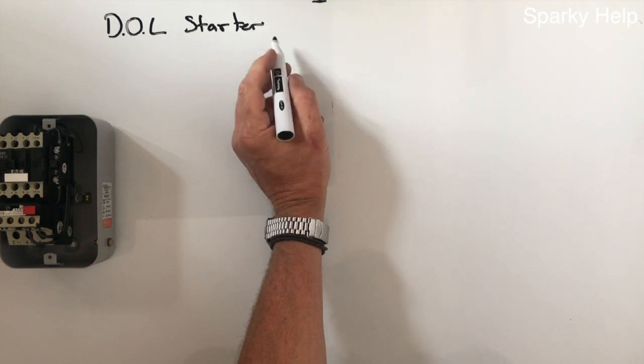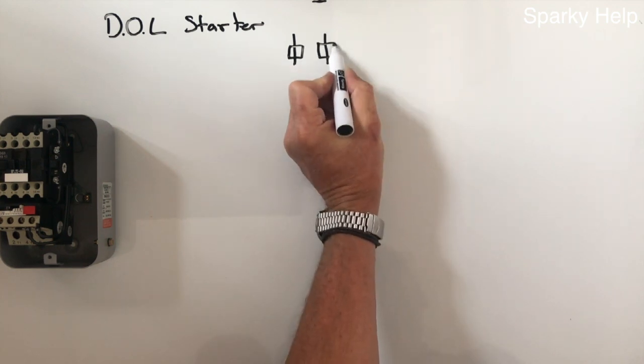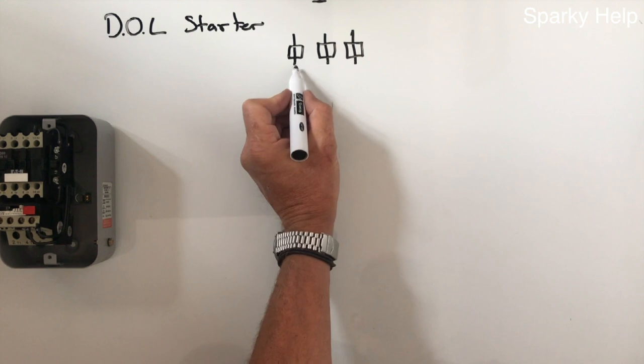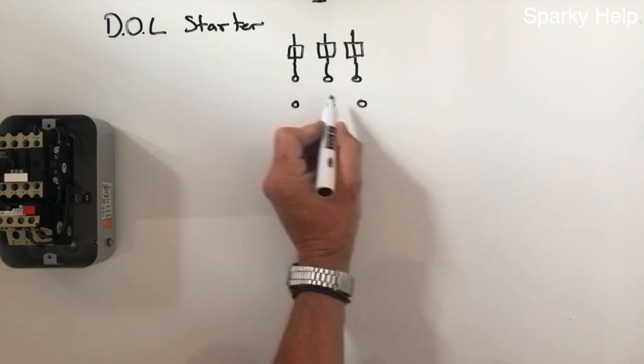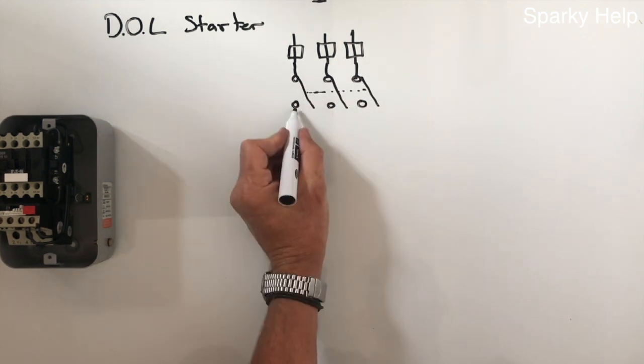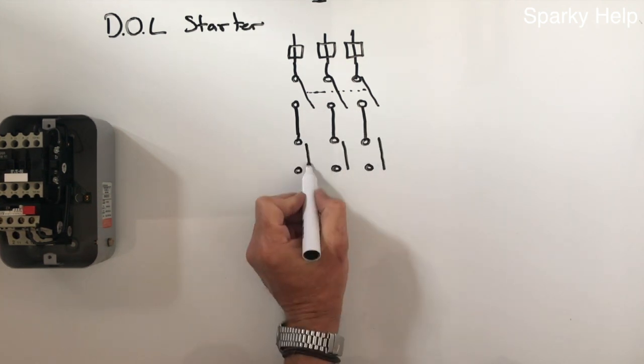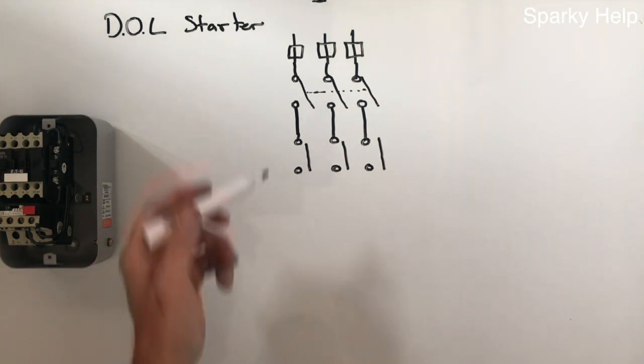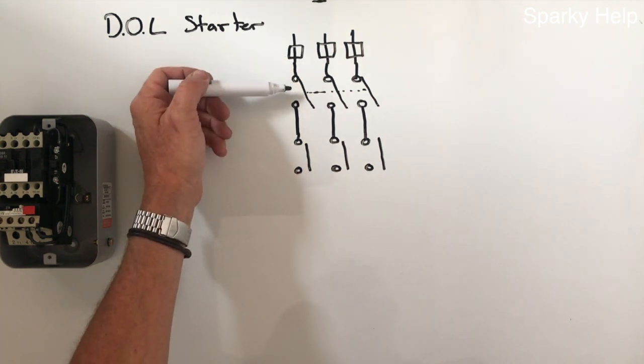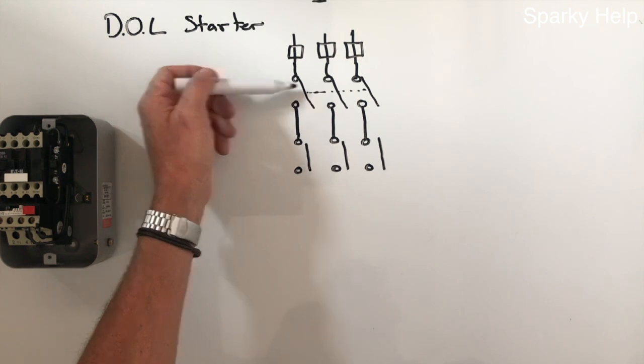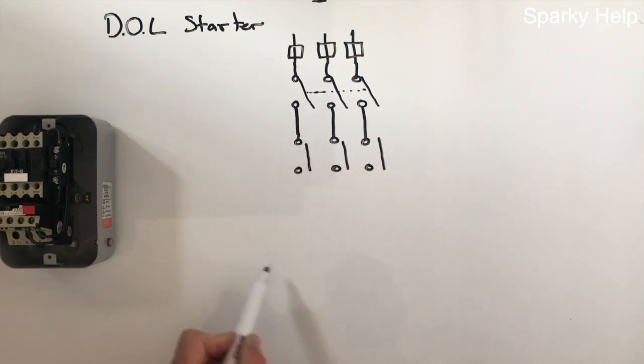All motors require some sort of fuse protection so let's do them as three phase. You'll then put some means of isolation in. So what we've got on here we have the fuses from your incoming supply for this circuit. An isolator, I've put triple pole in this and then we come into the motor itself. So from here on down this is going to be the motor.